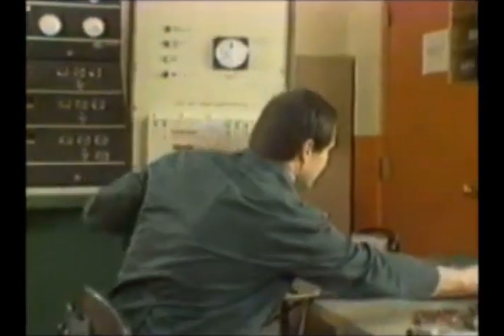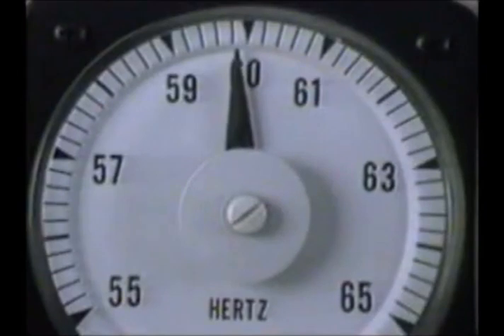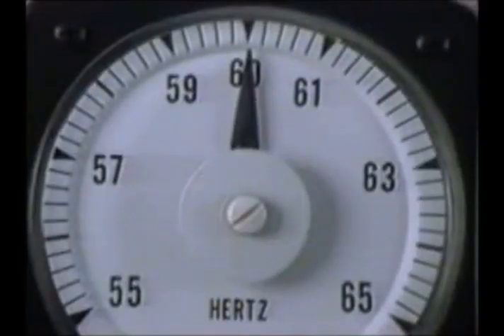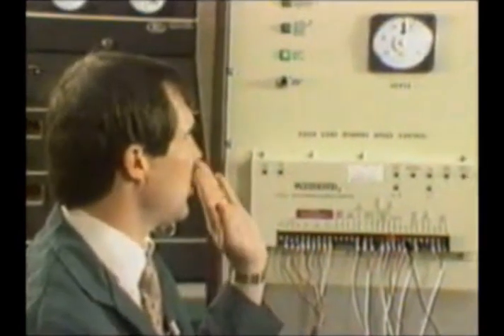And if you watch the Hertz meter, you'll see a slight off speed back to 60. That's a small amount of load. That's a 25 kW load step. Now I'm going to put on a 50 kW load step. And that's pretty quick and smooth, the reaction time. You see we go a hair off speed and back to 60.